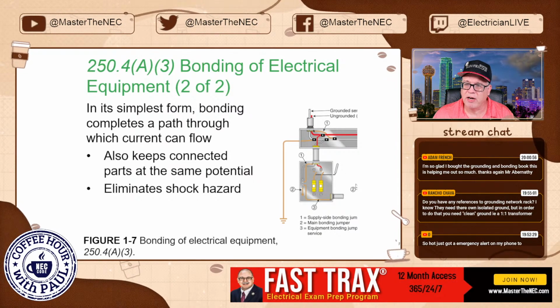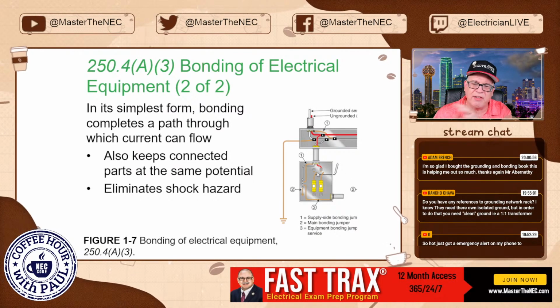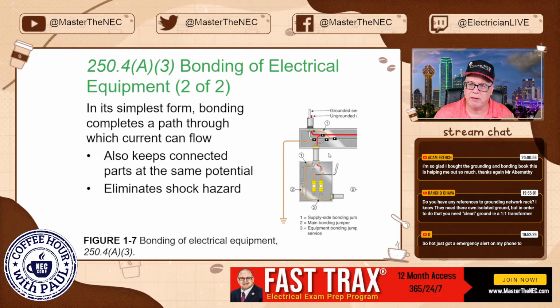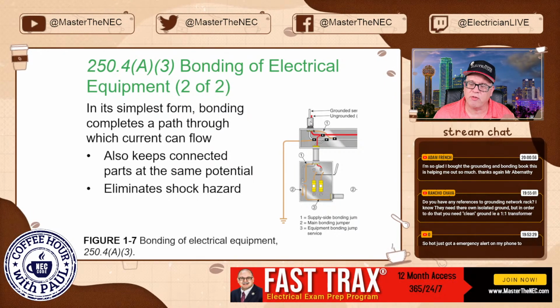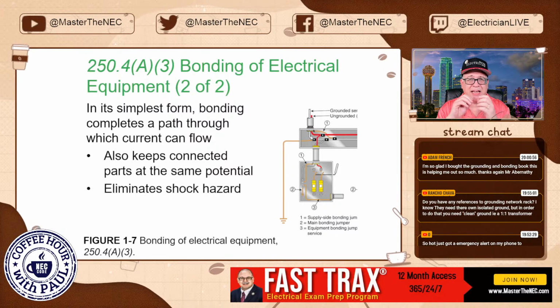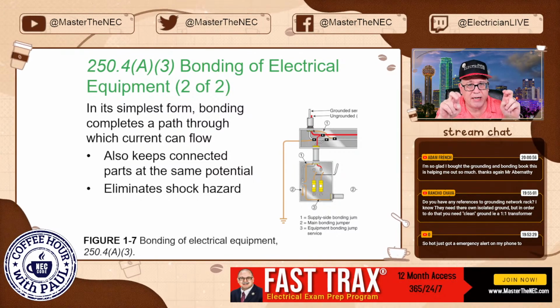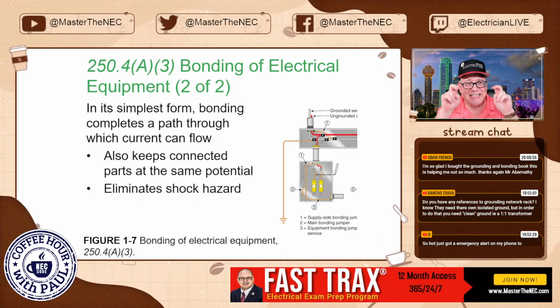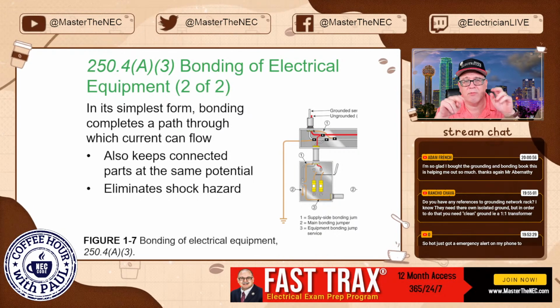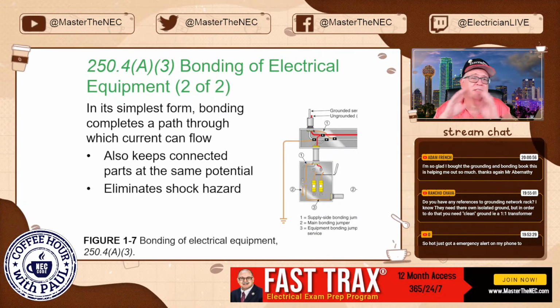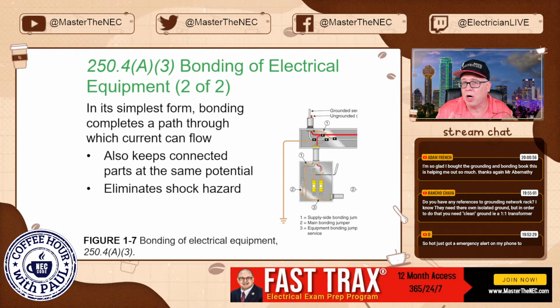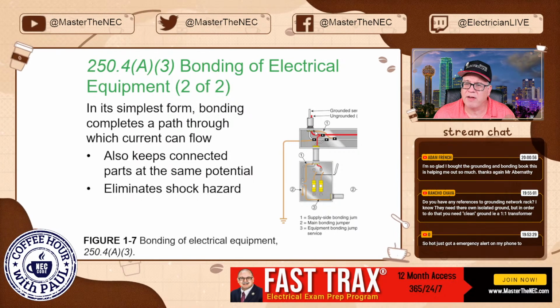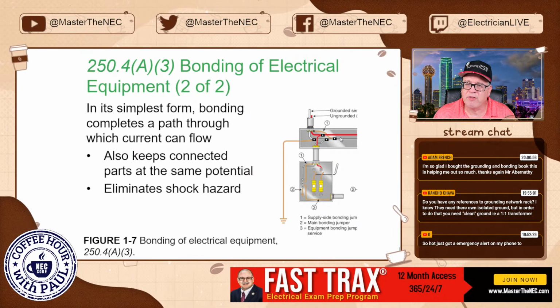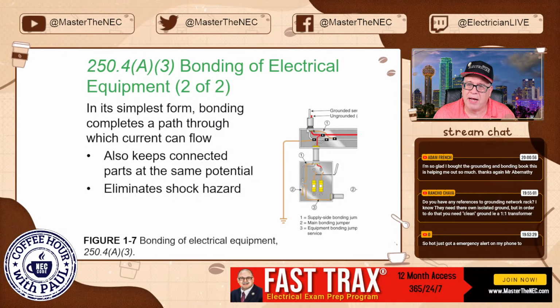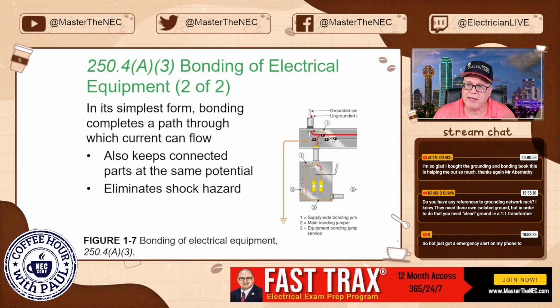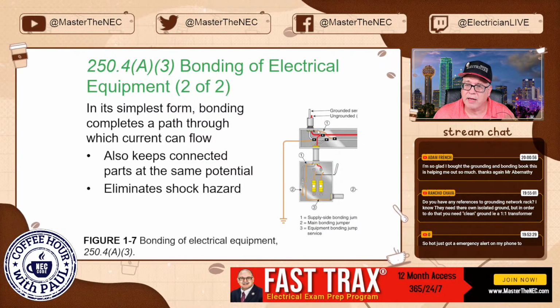All right, here's an example. I love illustrations, and Phil does these really well. Right here, here's your service raceway coming in. You have to do something like an assured bonding, a little extra bonding, per 250.90 and 250.92. If you have impaired KOs and things like that, you have to do a little bit more. Well, here you've got a bond right here. This is a supply side bonding jumper. You're bonding this raceway and everything to the grounded conductor. It's permitted in the code.